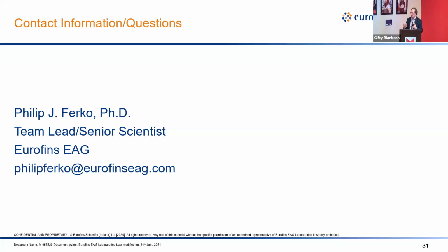And what's nice is it's soft enough that when you compress it on the ends, it'll form a good seal without needing an adhesive or a gasket, which leach a lot actually. Historically, people have known that's always been an issue. Gaskets are made out of elastomers, and it's been a problem for a long time. So I wouldn't say jury rig, but it was definitely something we developed internally to deal with that problem because there wasn't anything available commercially.